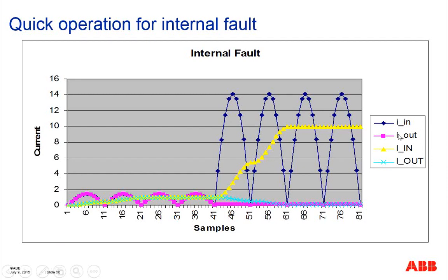The small i stands for a peak current, or just the raw measurement. The capital I stands for the RMS measurement, so it's the phase RMS measurement, estimated over a window. And the relay operates only on the RMS measurement. They don't operate on the raw or peak value.